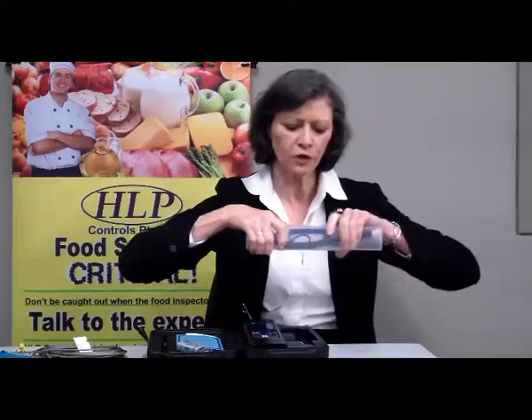All of these are just different styles of probe that you could order if it suited you, or we can just take an order from you. You can tell me what you need to measure, how you need to measure it, what temperature range you want. This unit has a very, very wide temperature range. It will measure anything from -50 up to plus 1300 degrees with an appropriate probe. You don't want to be measuring 1300 degrees when you're only this far away from it.